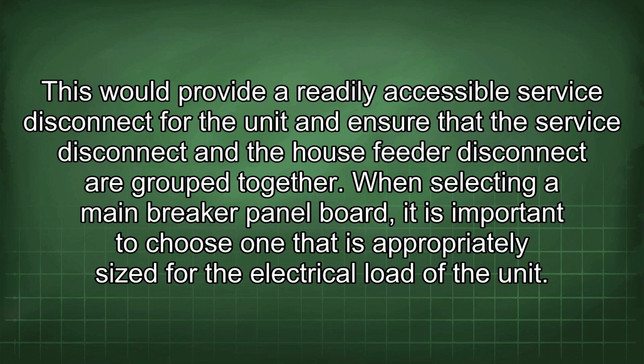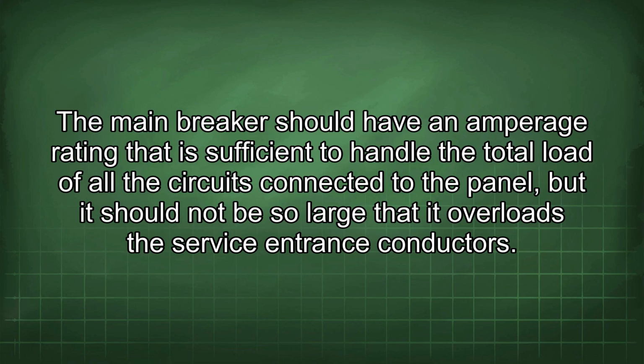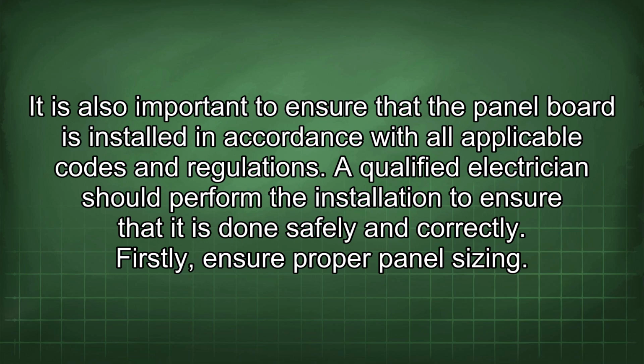When selecting a main breaker panel board, it is important to choose one that is appropriately sized for the electrical load of the unit. The main breaker should have an amperage rating that is sufficient to handle the total load of all the circuits connected to the panel, but it should not be so large that it overloads the service entrance conductors. It is also important to ensure that the panel board is installed in accordance with all applicable codes and regulations. A qualified electrician should perform the installation to ensure that it is done safely and correctly.